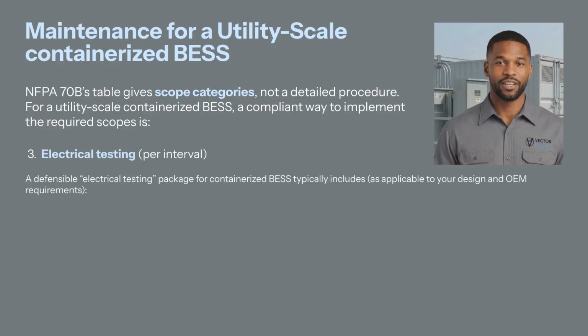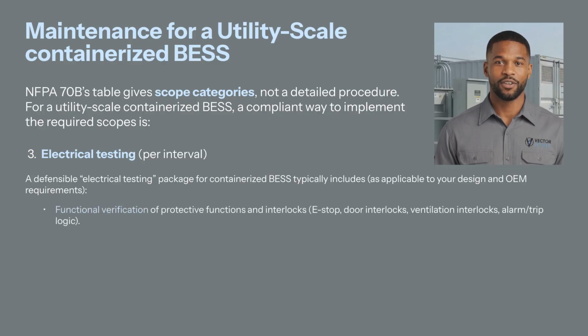3. Electrical testing per interval. NFPA 70B recognizes that intervals may be driven by continuous monitoring or predictive techniques, and that testing should align with manufacturer and industry practices. A defensible electrical testing package for a containerized battery energy storage system typically includes, as applicable to your design and OEM requirements, functional verification of protective functions and interlocks: e-stop, door interlocks, ventilation interlocks, alarm trip logic.